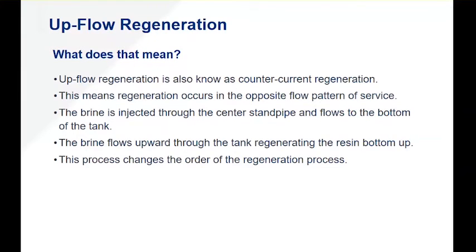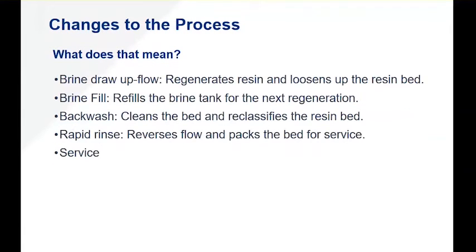The process changes the order of steps. The first thing we're going to do is go through brine draw — draw the brine out of the tank. Some of these systems will actually start off by putting water into the brine tank, waiting two hours, then starting. You're going to regenerate from the bottom up, which slightly loosens up the bed and will carry out some of the dirt to waste. Then it's going to go into brine fill and fill the brine tank back up for the next regeneration. Then it's going to go into backwash. But if you're backwashing with hard water, you're running hard water from the bottom of the tank up, and now you have hardness on the bottom of your resin — that's why regeneration with soft water is the way to go with upflow brine.